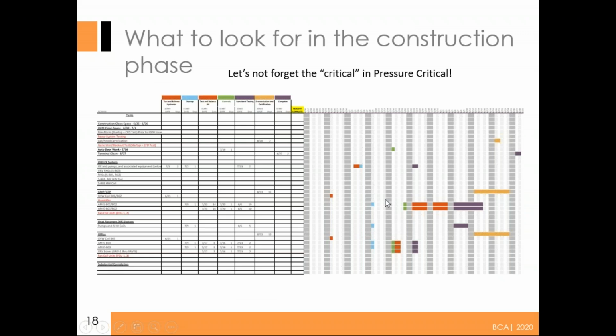So it's not just pressure critical, it's critical. These are typically the most revenue generating spaces in hospitals. So if you're doing a replacement hospital, maybe you've got a few months to get the bugs out of some of these rooms. But if you're just doing a pharmacy renovation in an existing hospital, or some sort of clean room or lab in a hospital, there might not be a lot of that kind of buffer time.